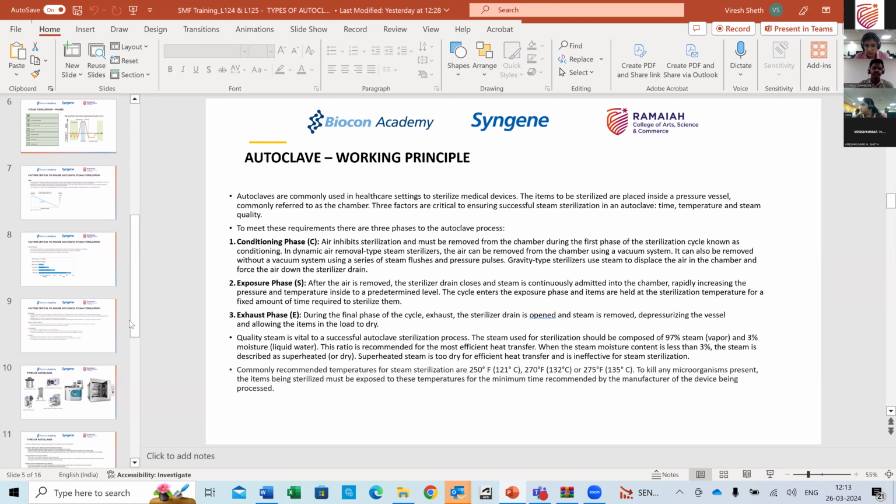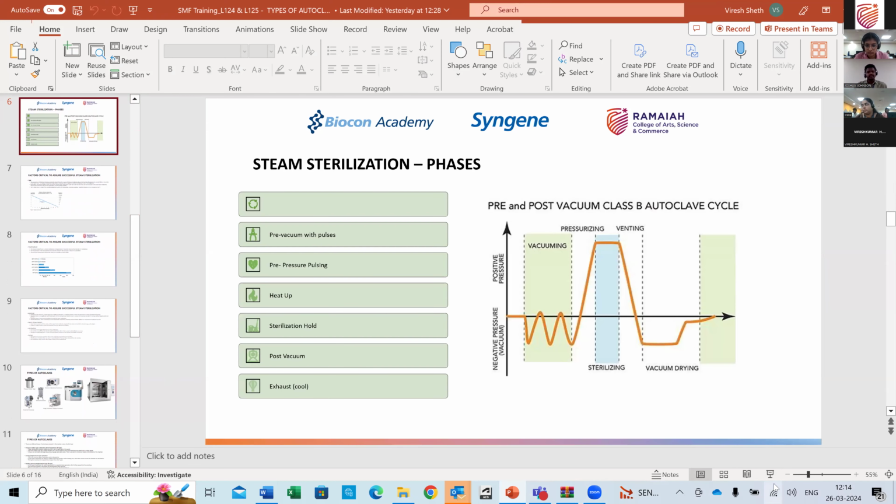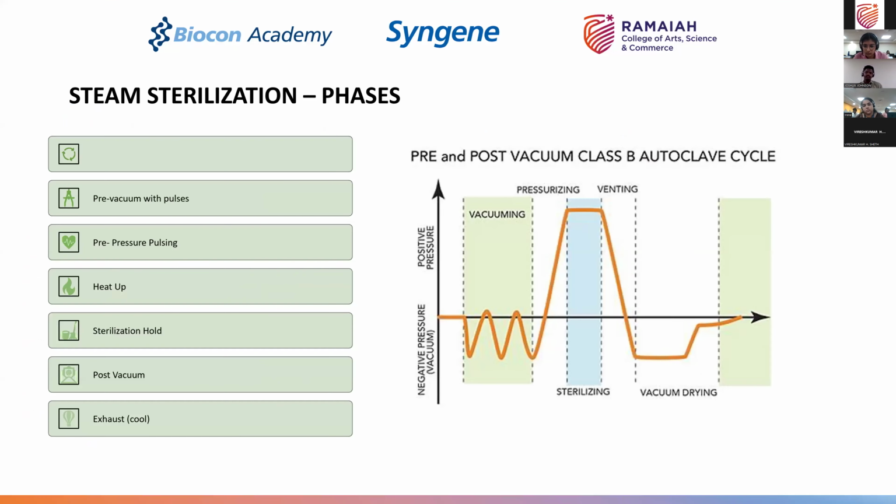So can you explain the sterilization phases, sir? Sure. Let me go to this slide because this is more what you're going to see. What are the factors which are important for any sterilization? There should be no air inside the chamber, right?